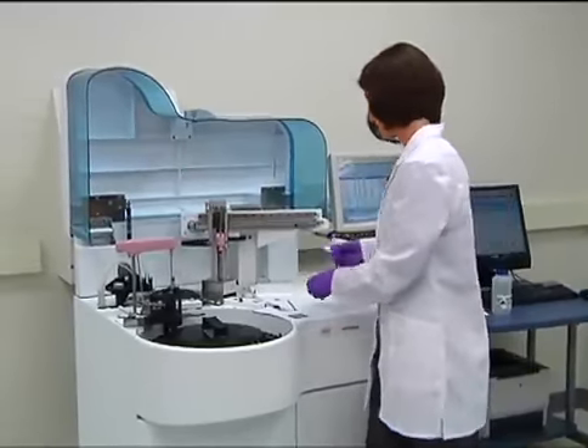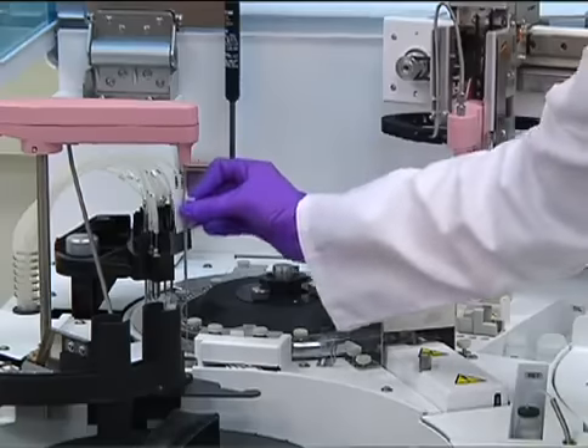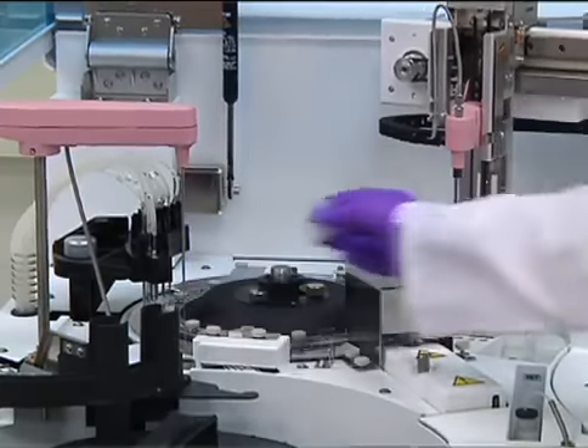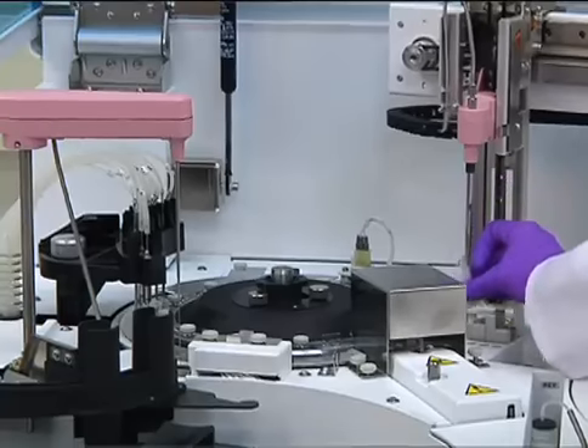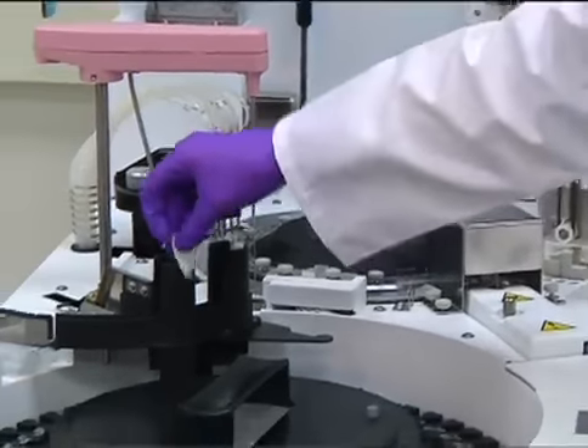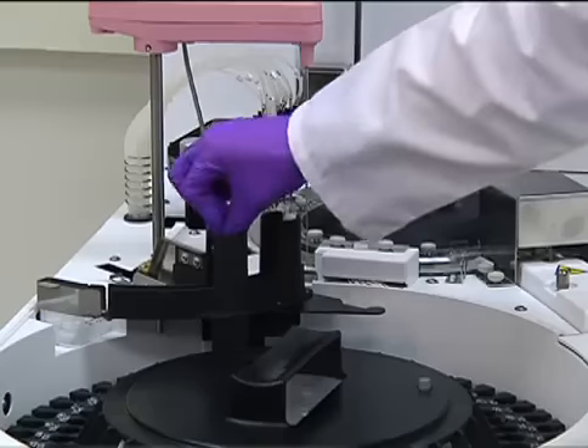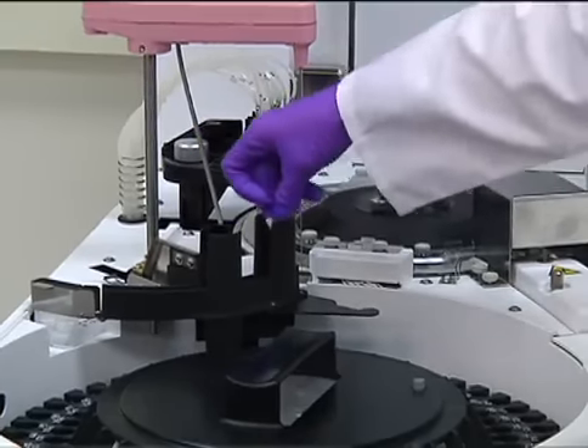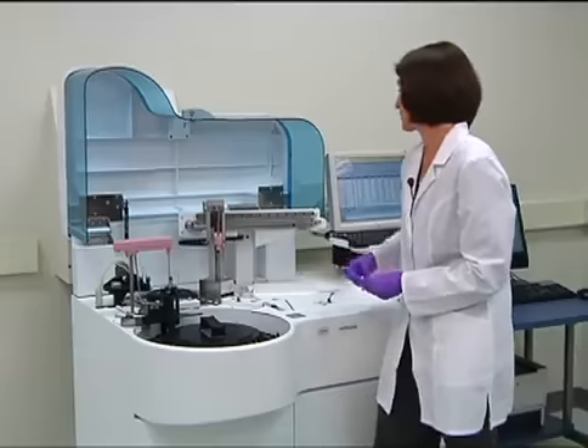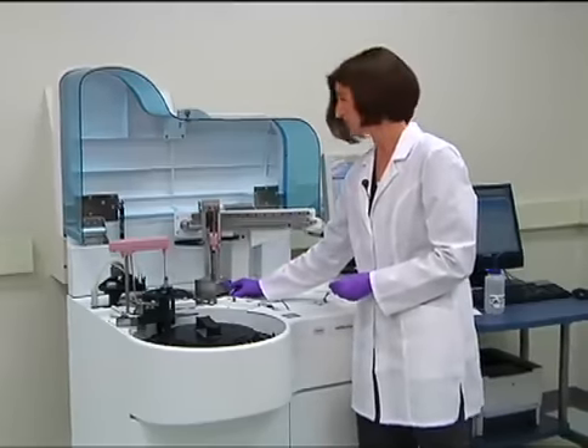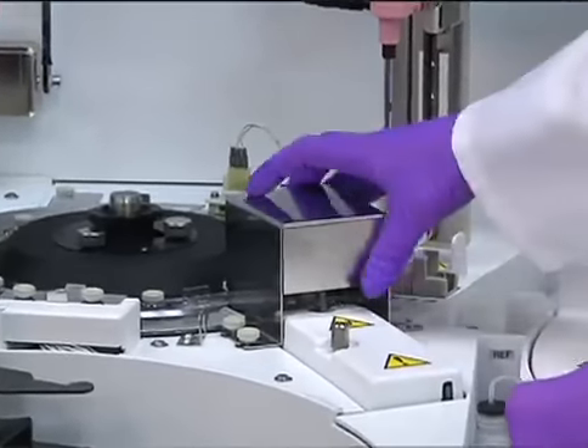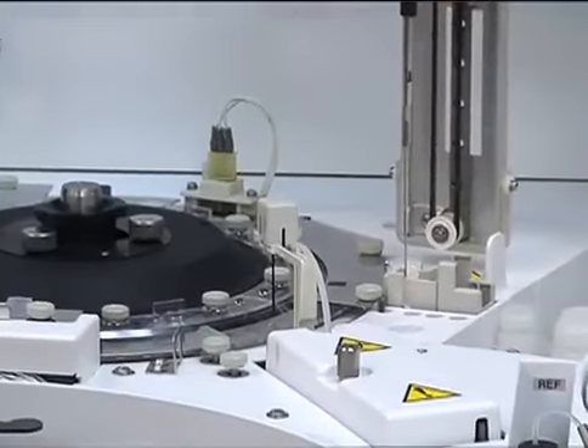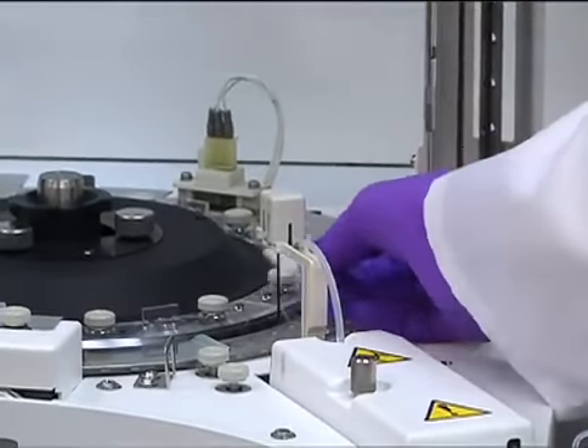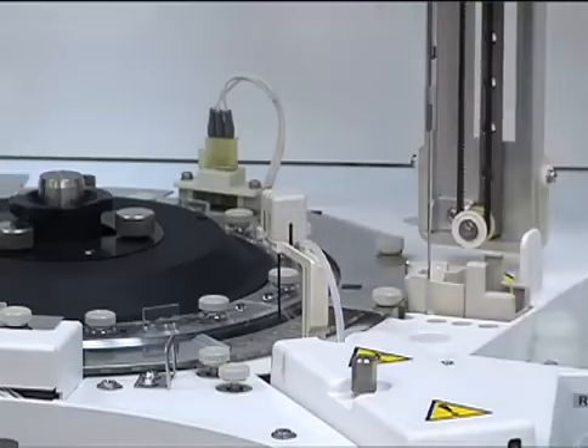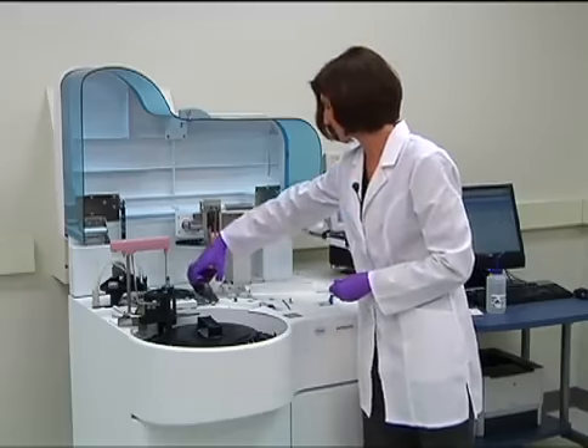So we'll take the alcohol pad and we will wipe down the length of the sample probe, the length of the reagent probe. We will clean the shield pipe where the sample probe goes in to pipette the sample. Then we will remove the sipper nozzle cover and wipe down the sipper nozzle. Then we will return the cover and tighten it back in place.